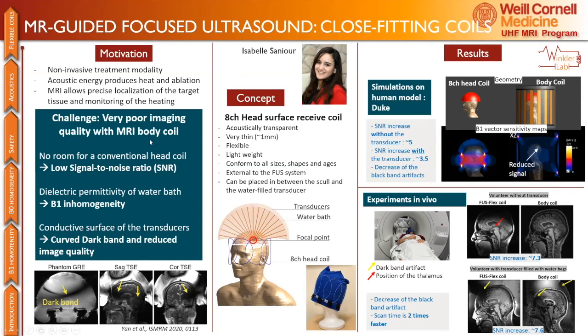But the challenge is that the imaging quality is so poor because people use the body coil. You have this transducer helmet around your head, so you can't use the head coil, right? And then, of course, that transducer has a shield. So now the RF energy just can't really come through, and it's basically a disaster, if you ask me. So you get these dark bands and very low signal, and it's really not great. So what Isabel came up with here is an 8-channel surface receive coil based on GE's air technology. It's acoustically transparent.